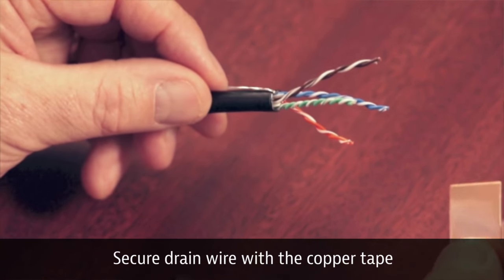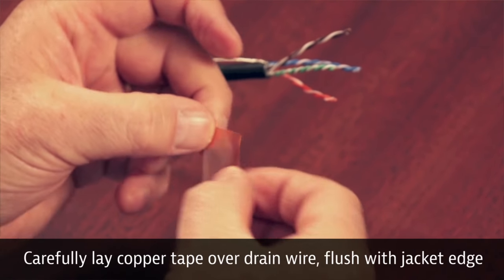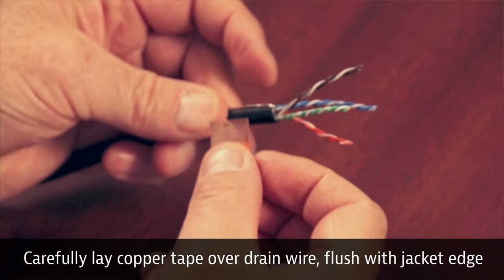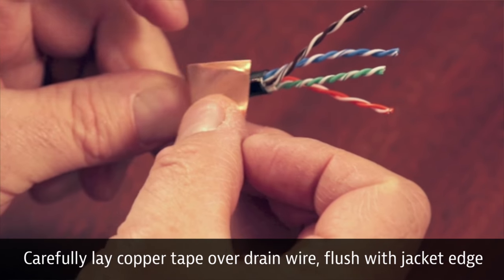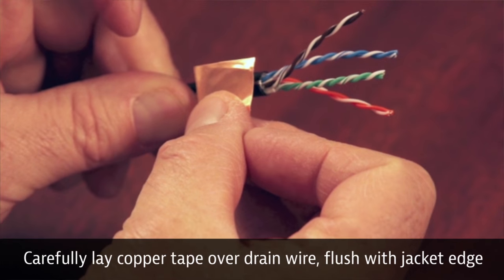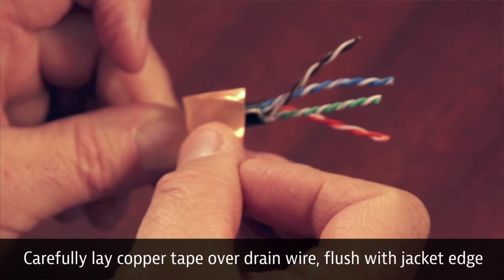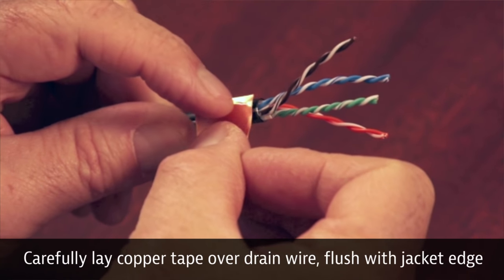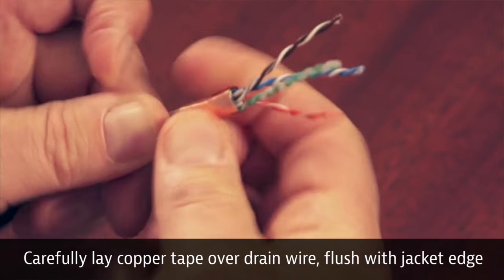I'm going to peel off my copper tape. I want to be careful not to cut my fingers - copper tape can cut also. I want to lay this copper tape over the drain wire and flush with the end of the jacket. I don't want to go over the end of the jacket because that copper tape edge can be sharp and cut into the insulation of the conductors. Line it up and rotate it around to give it good coverage.